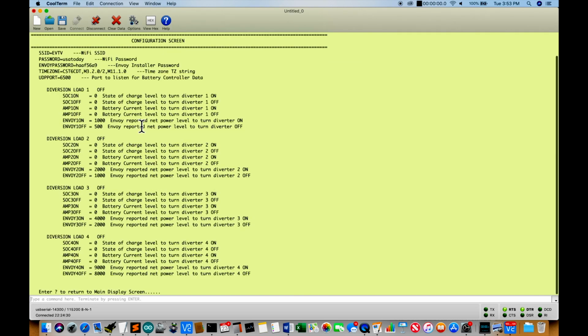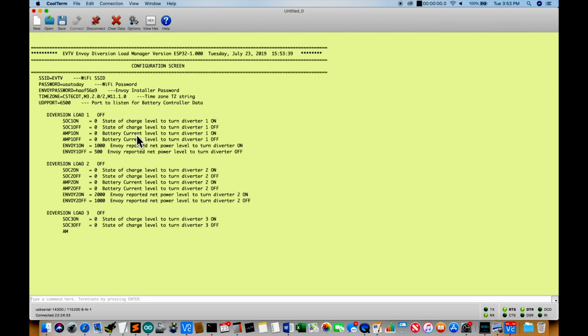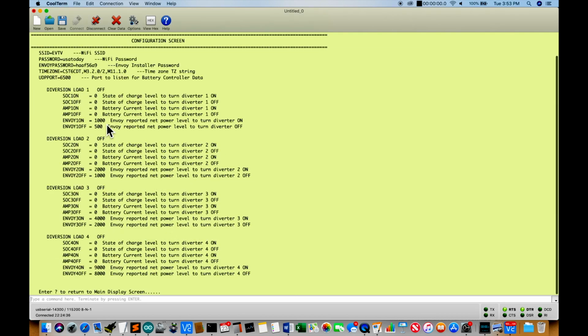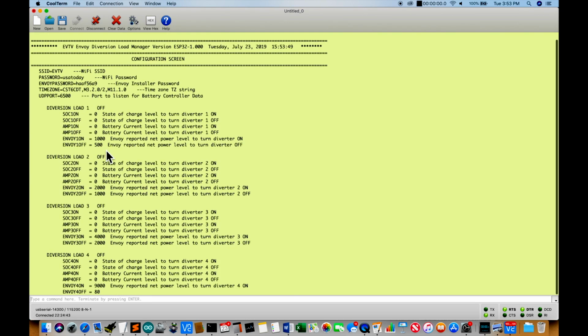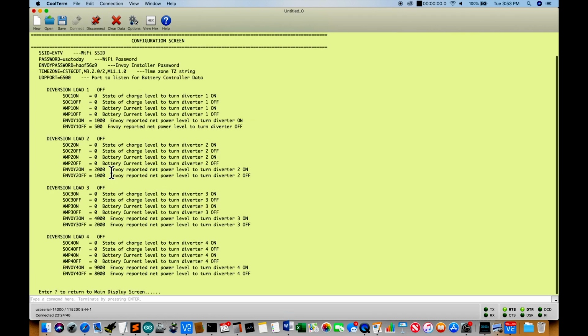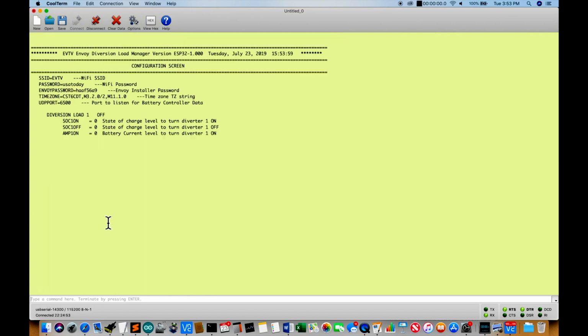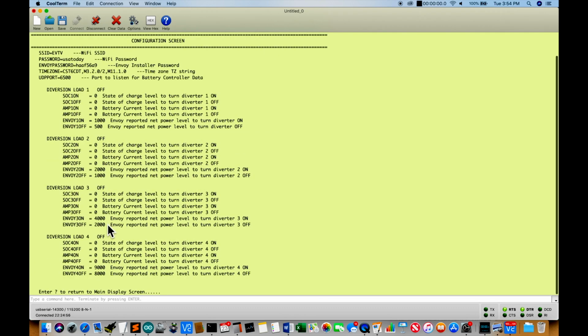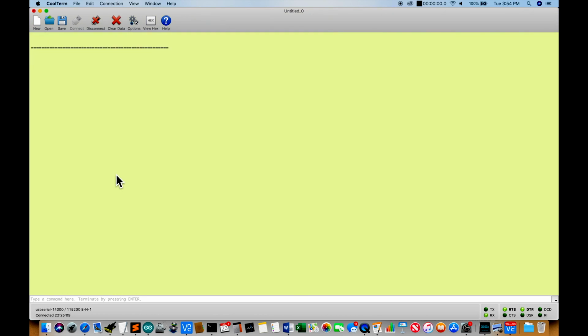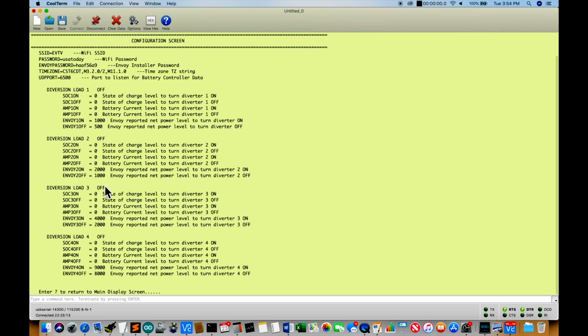That's the produced power minus the consumed power. You have a net power level, and Envoy 1 we turn on at 1,000 watts of net power and off at 500, while Envoy 2 we turn on at 2,000 watts and off at 1,000. Load 3 we turn on at 4,000 watts net power and off at 2,000. Load 4, a big load, turns on at 9,000 watts and off at 8,000. It's kind of progressive, and you can do this in a lot of different combinations to control those 4 outputs.